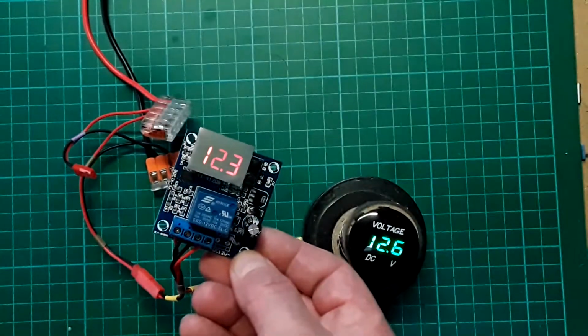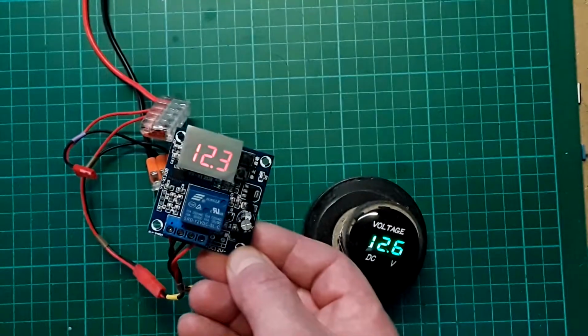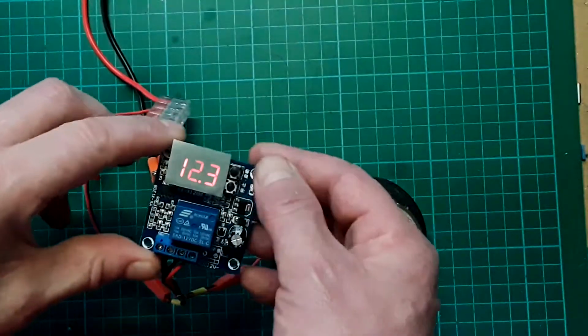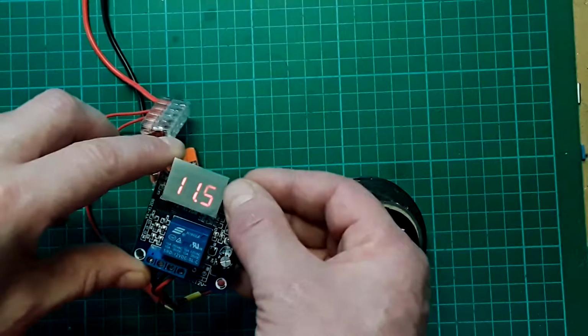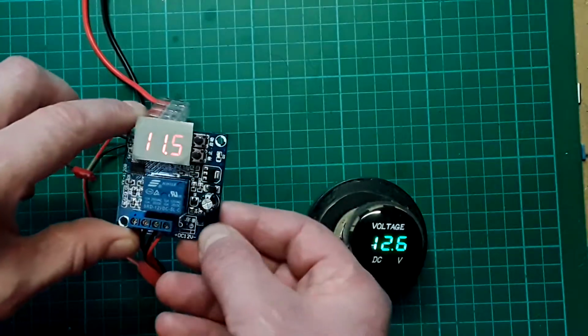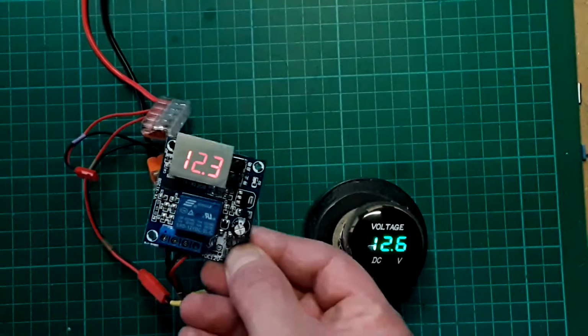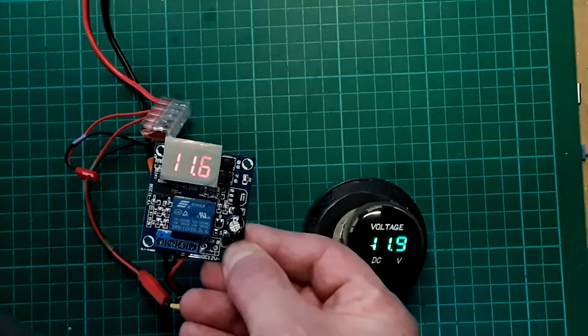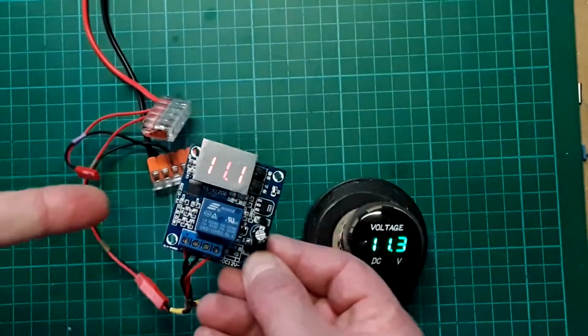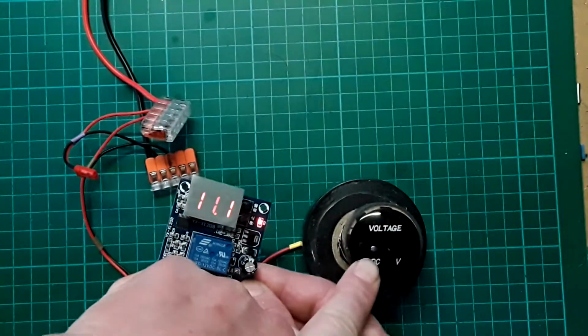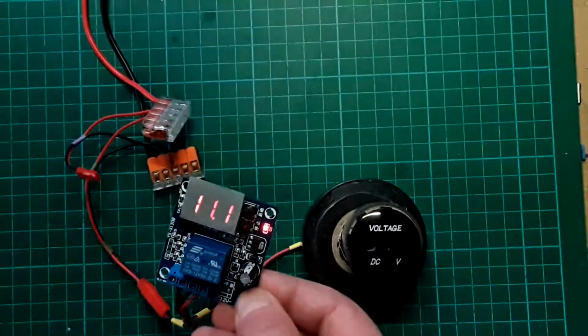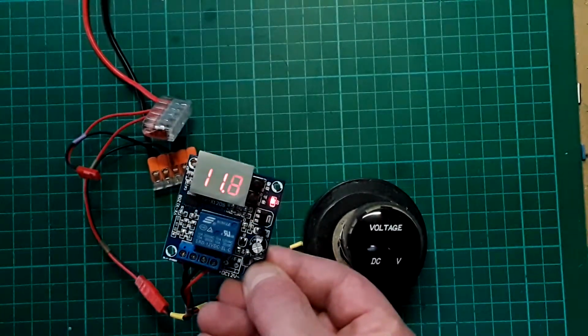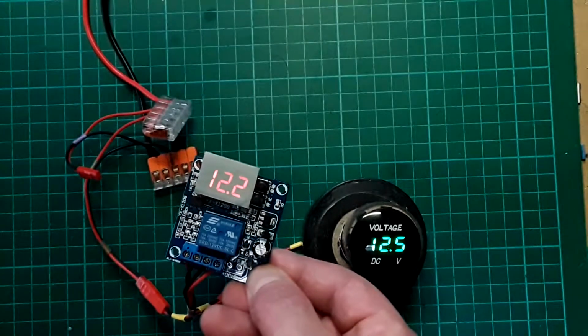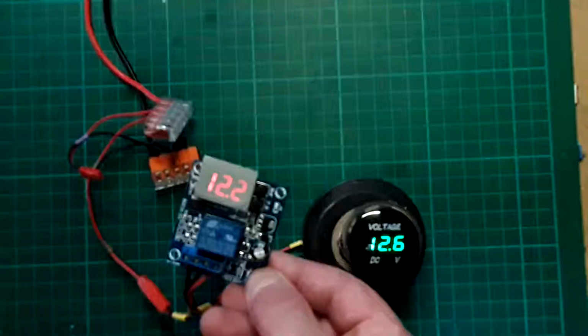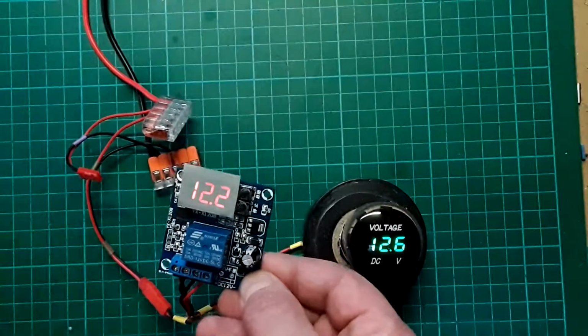Go on, is it going to humour me? No, it's not, is it? What's going on here then? Oh, did I set it wrong? Hang on, yeah, I didn't set it back. No, 11.5, yeah, so I want to go down to 11.5 - excuse me, brain fart. 11.5, yeah, and we're below 11.5. Nothing's happening for the moment until a time delay, and then it's gone into fault mode and disconnected the output. If I go up above 11.5 - oh yes, we've gone above 12 now, haven't we?